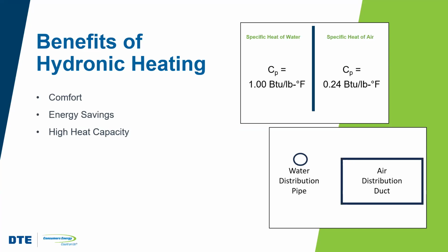And so, considering the density of both of those fluids, volume for volume, water has a heat carrying capacity that's roughly 3,400 times that of air, right? So, if you had a cubic foot of air and, converting gallons into cubic feet, the same volume, right? A cubic foot of water, right? The water would have a carrying capacity of 3,400 times that of the air.